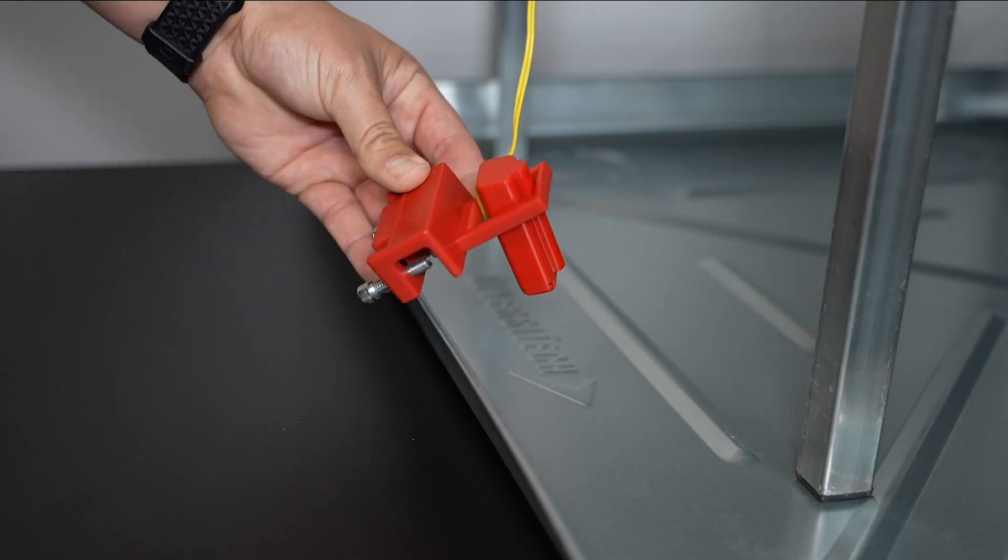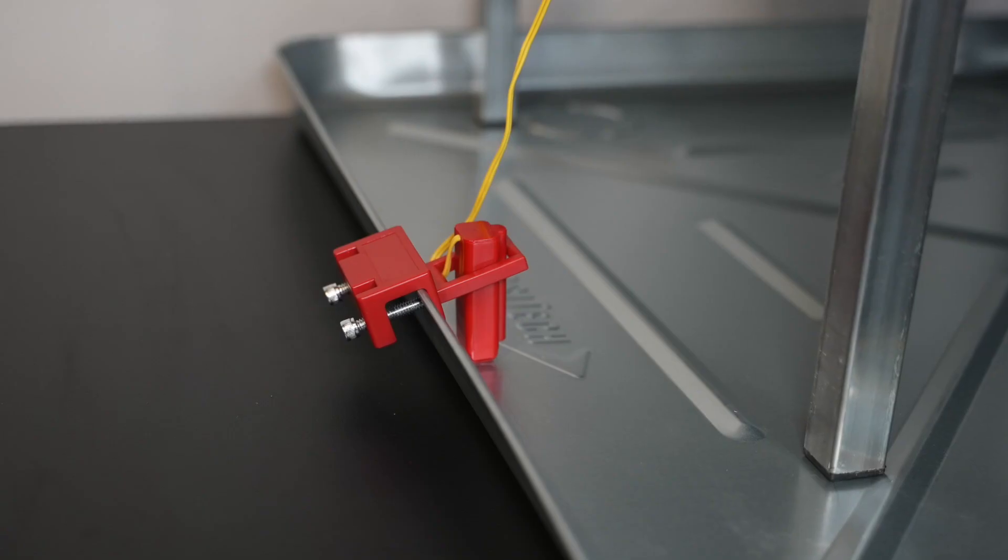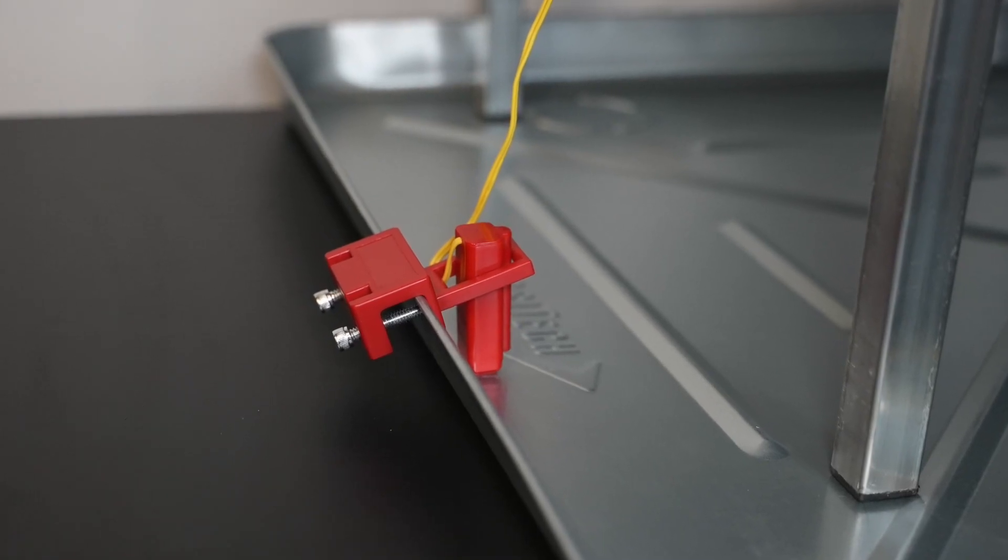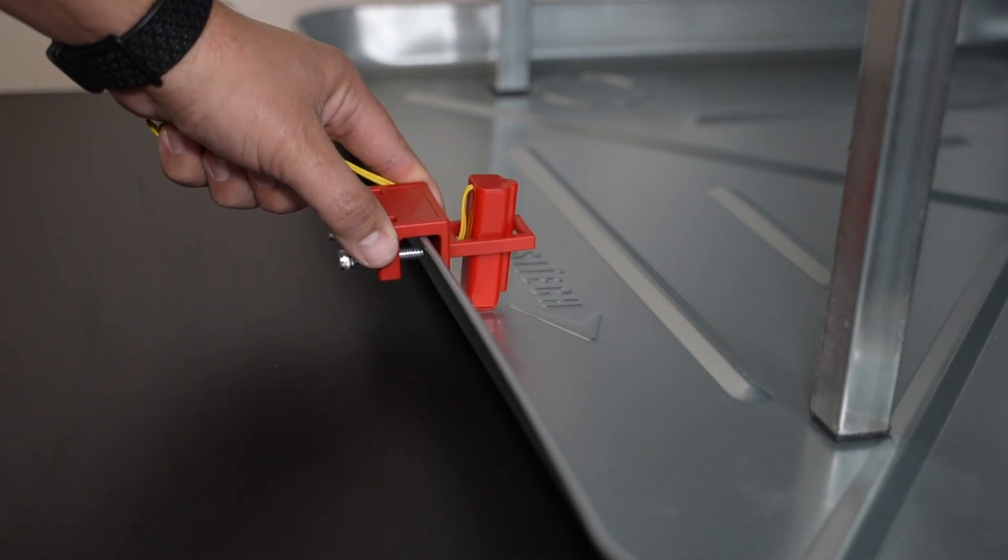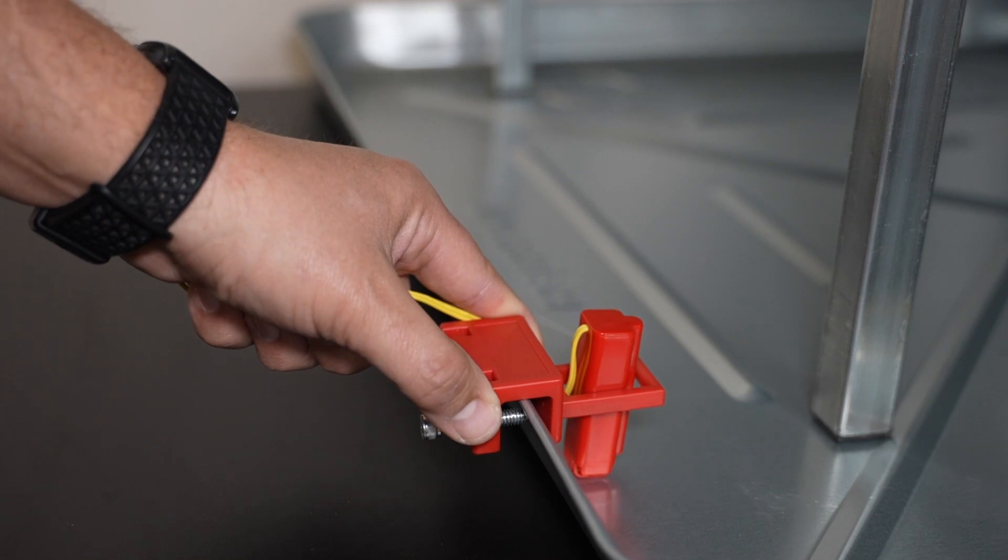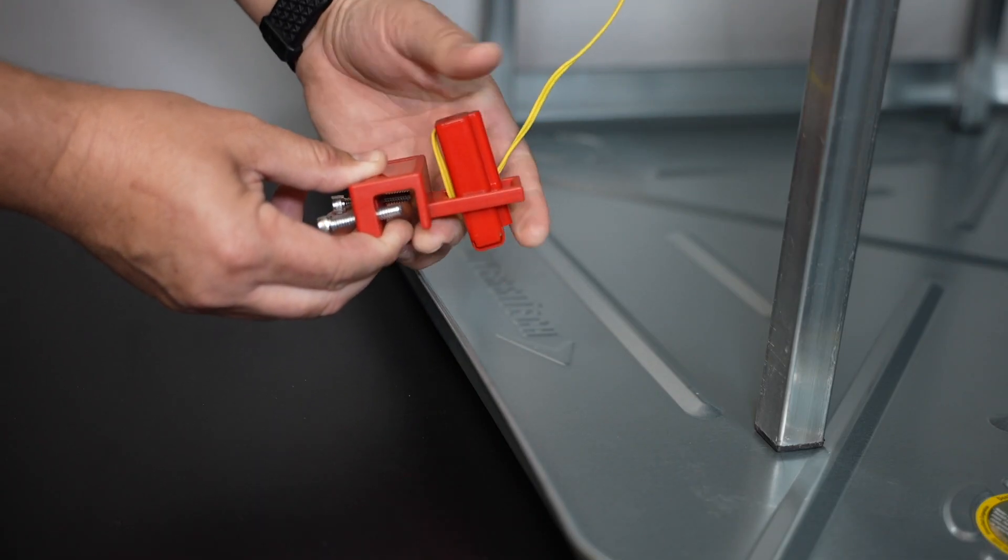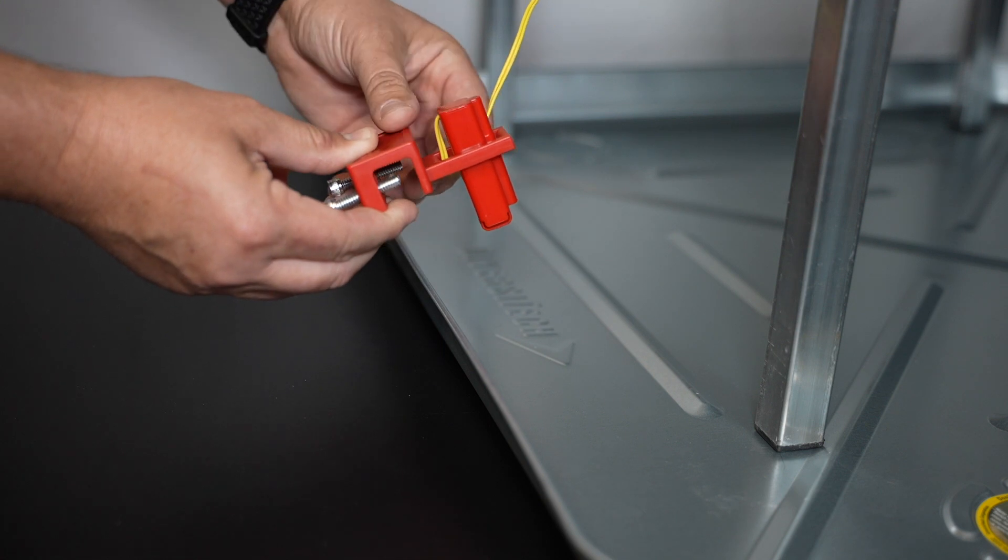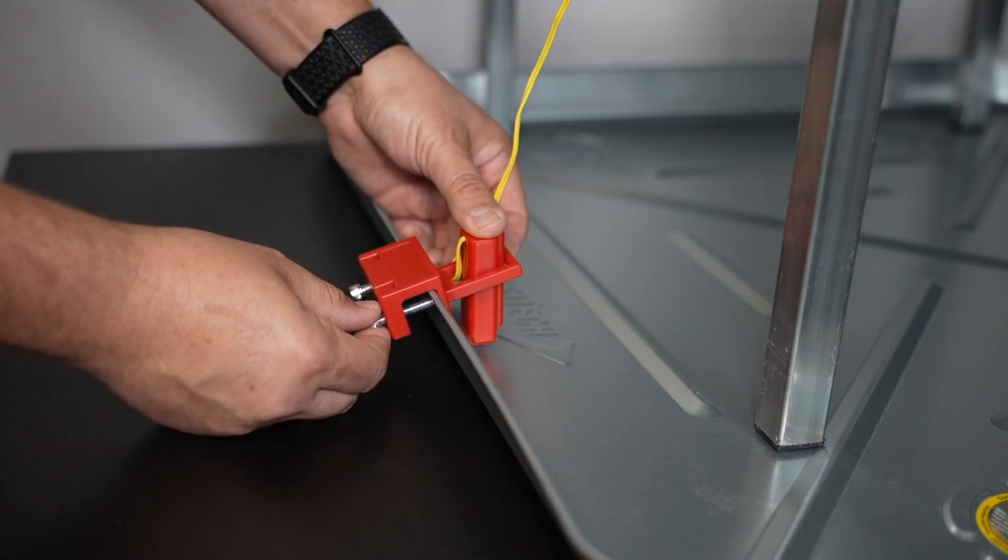Now let's take a look at Assurity's secondary pan switches. The CC1 condensate overflow switch is a clamp-on style switch designed for the secondary pan. Its design lets you clamp over the edge of all drain pan types. You can easily position it anywhere along the drain pan. It has adjustable activation height with a minimum of an inch and a half. The sensor assembly swivels for drain pans with sloped sides and it's for standard rated installations in pans.